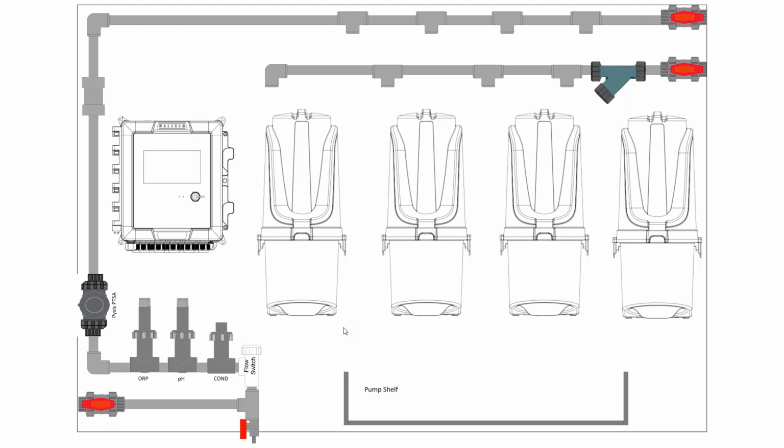Well, like I said, we've talked about this now 5 times, and I'm happy to say it another 10 times: if you're using city water with some sort of pre-filtration, the likelihood that you're going to get something that's really going to screw up your float is less. That's where you reduce that, versus something that's going to get in there and jam it up over time. That's correct.